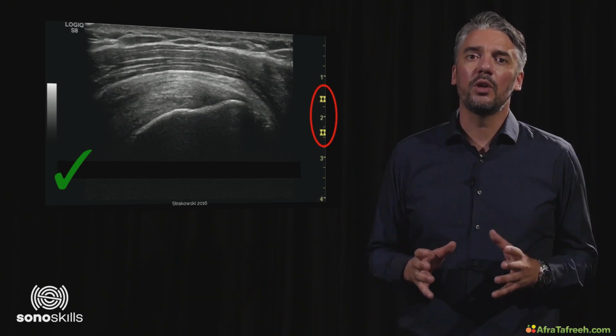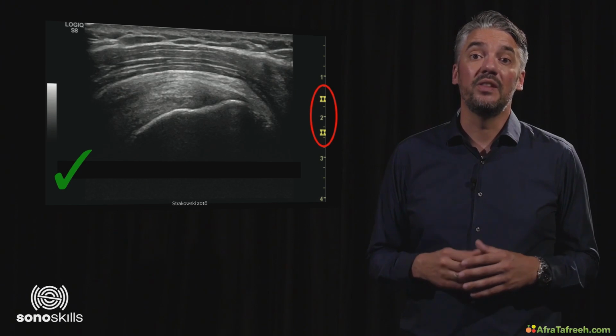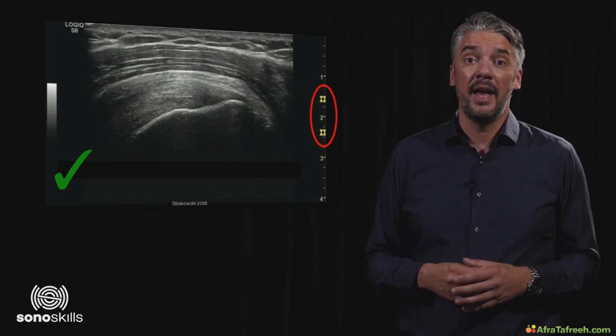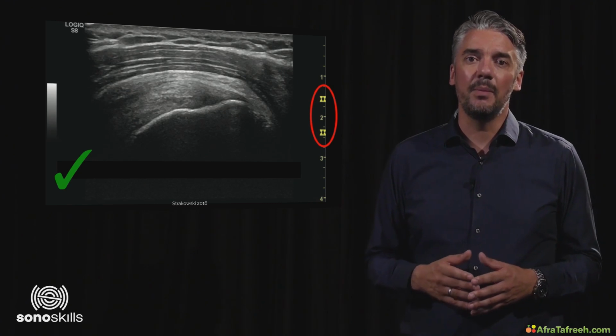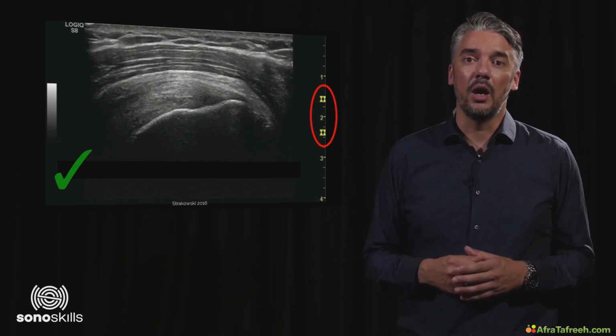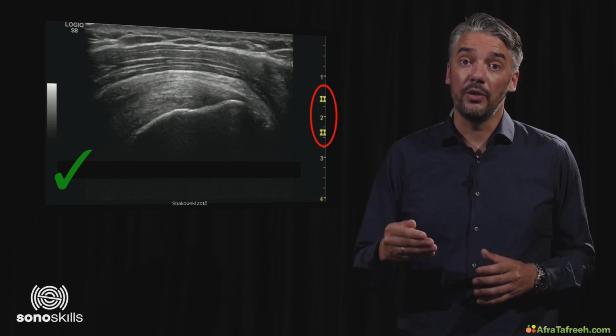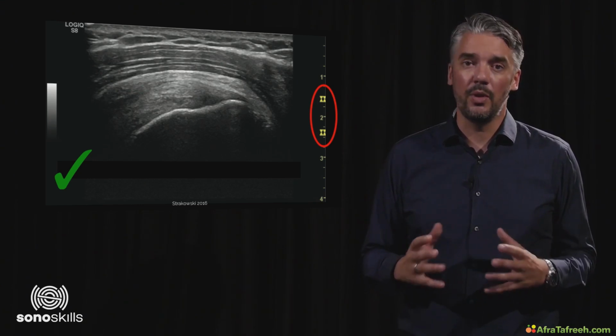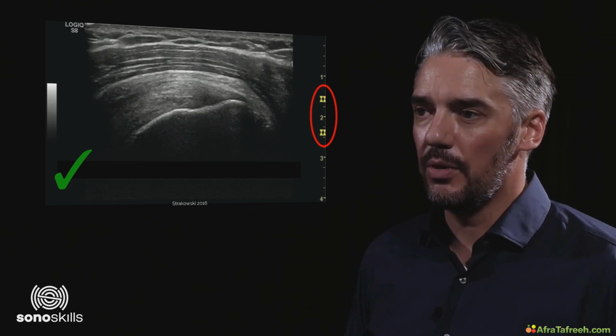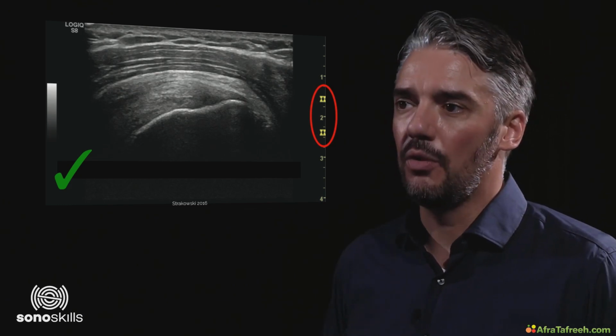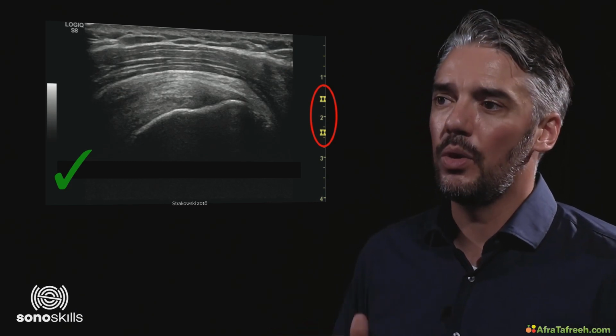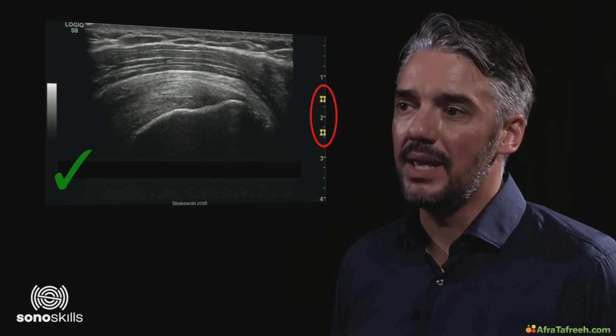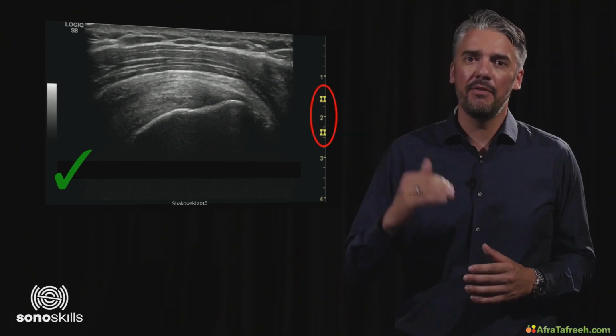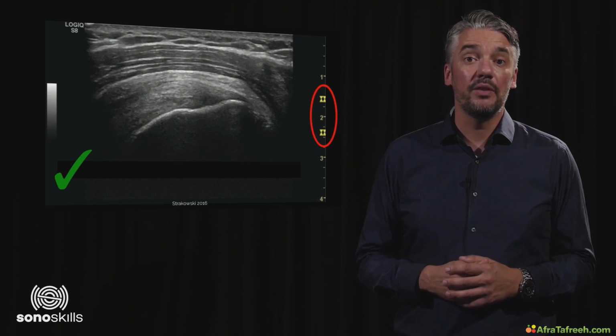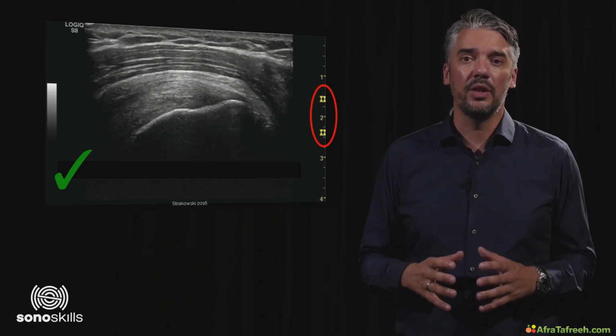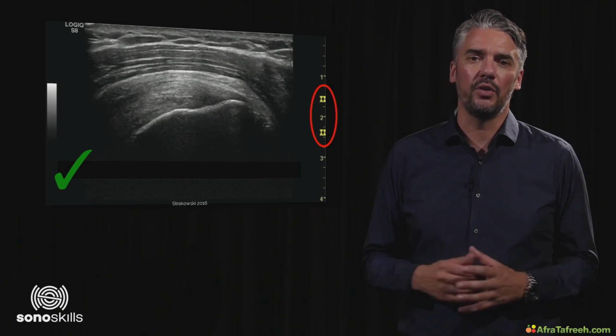However, the focal point will correspond approximately to the deepest part of the Fresnel zone, and as such, any part of the image deep to the focal point will lie within the Fraunhofer zone with associated beam divergence and poor resolution. Consequently, much better results will be achieved by placing the focal point roughly level with the deepest part of the structure to be examined. Everything above this level on the screen will be within the Fresnel zone and will therefore lie within the region of relatively high resolution.